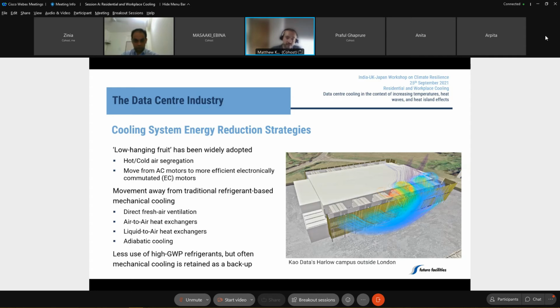And all of these can be aided through the use of adiabatic cooling or evaporative cooling, as the preceding speaker mentioned. And the image on the right is actually of a site in the UK that we at Future Facilities have worked with, where they use air-to-air heat exchangers and adiabatic cooling for the entire cooling system of their multi-megawatt data center, with no refrigerant-based cooling at all.